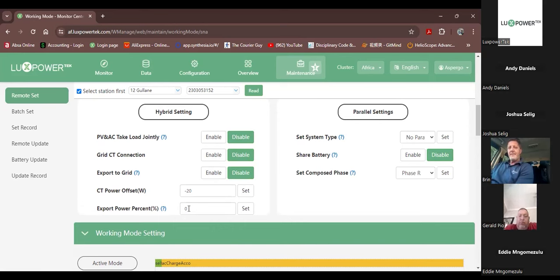What this allows you to do is export excess power. In other words, you're harvesting PV, it will first supply load, then charge the battery, and any additional power that is left over will be exported to grid. And this percentage value here is, you can say, I want to export 100% of my excess PV, or I want to export 10%.